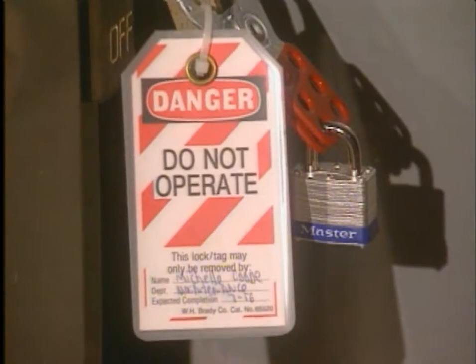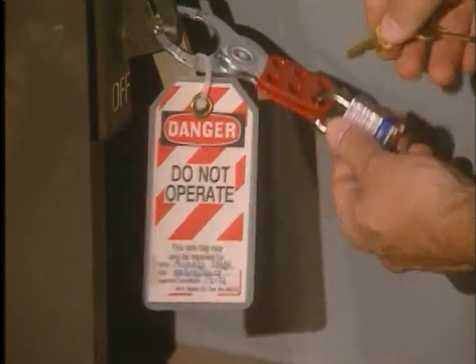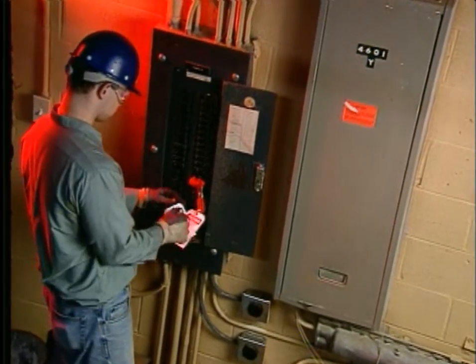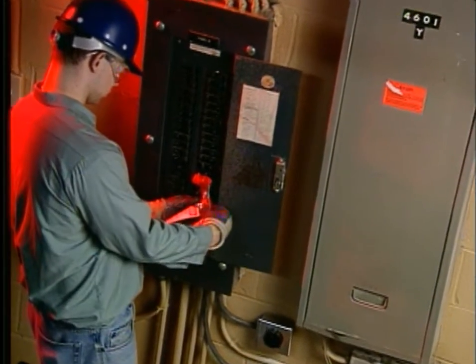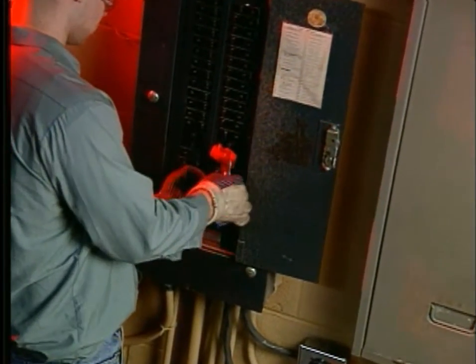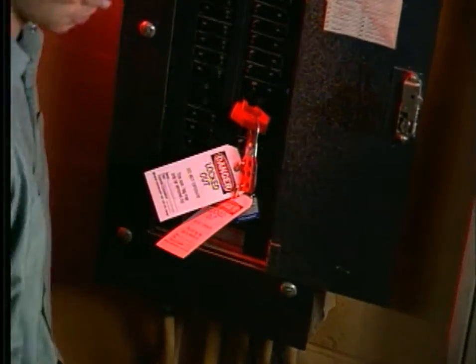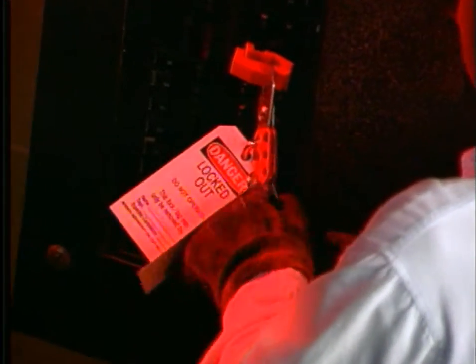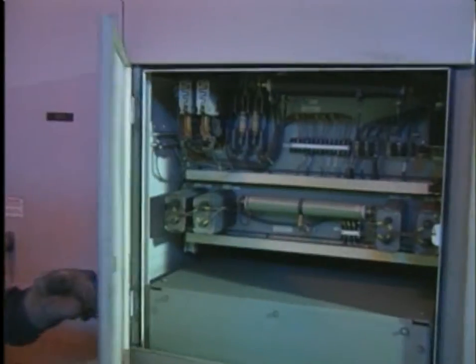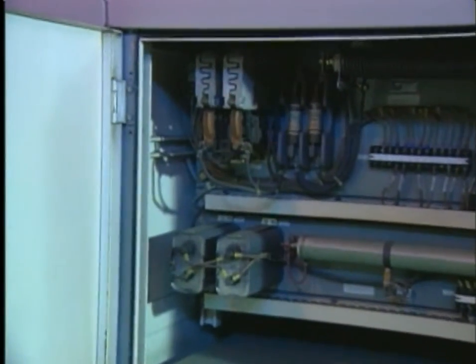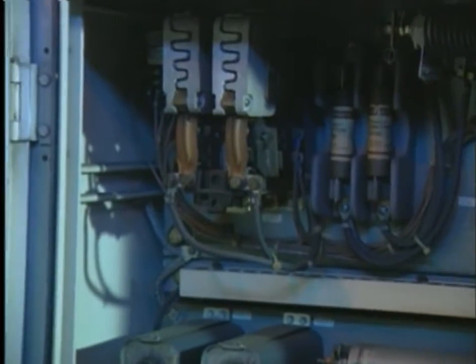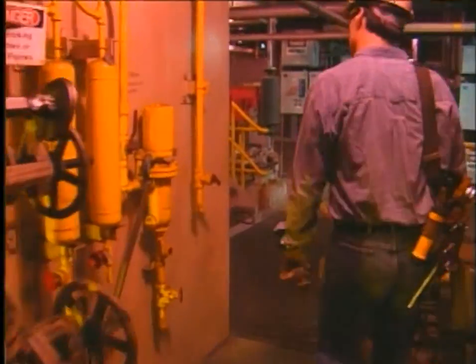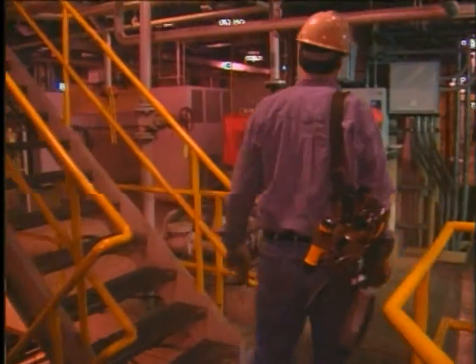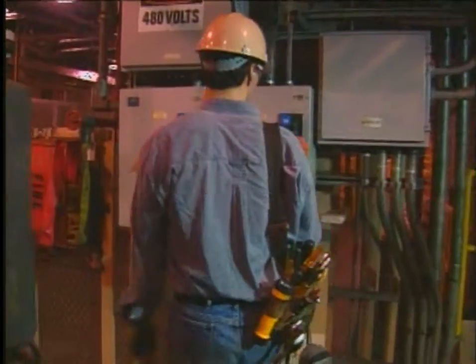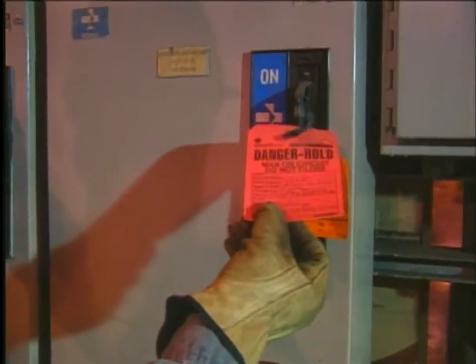Never remove a lock or tag applied by someone else. If work extends beyond one shift, the off-going shift removes their locks and tags, and the oncoming shift applies their locks and tags before starting to work. Conductors and parts of equipment that have not been locked out or tagged are treated as if they are energized. Even if the equipment is locked out, don't assume freedom from electric shock. It's possible that energy from an additional source can still provide a deadly shock.